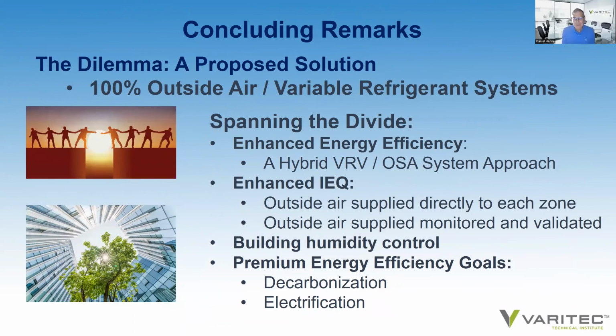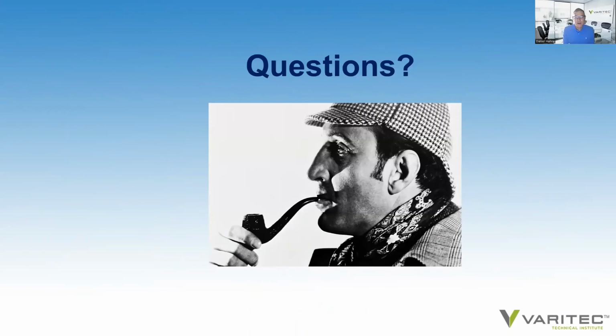So to span that divide, I suggest that we look more closely at 100% outside air variable refrigerant systems to span the divide that we have before us, to allow for enhanced energy efficiency, provide enhanced IEQ, and provide better building humidity control while offering premium energy efficiency on system concepts, if we choose to evaluate them.